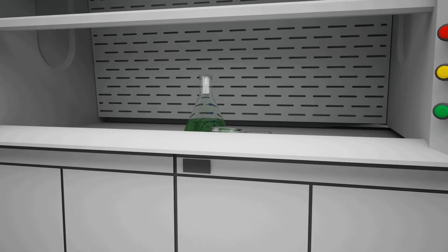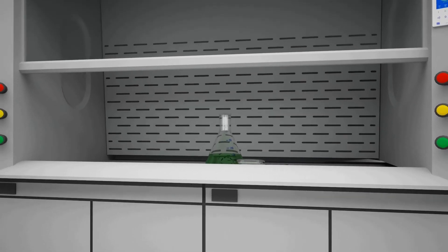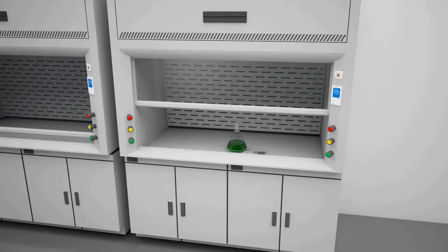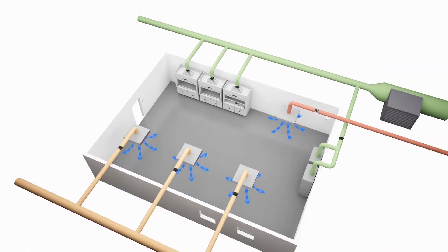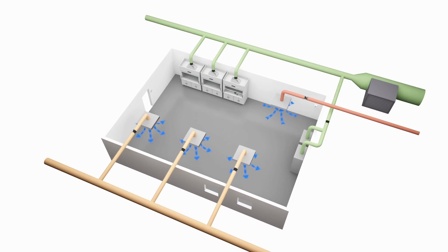TEL's auto-sash controller will work with VAV fume hoods and also on CAV fume hoods, and can be fitted to new or existing fume hoods with a choice of three motor drive systems, which will suit most types of fume hoods.